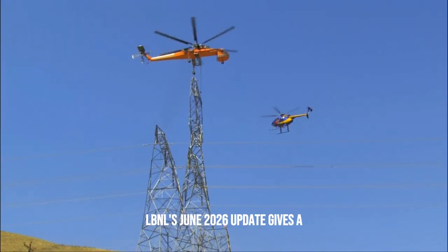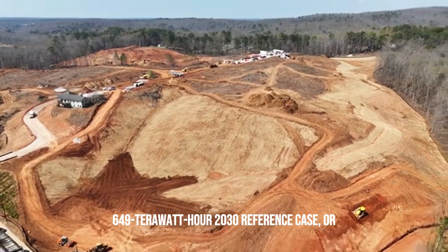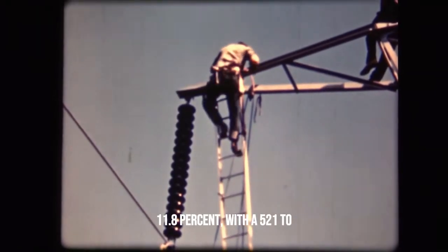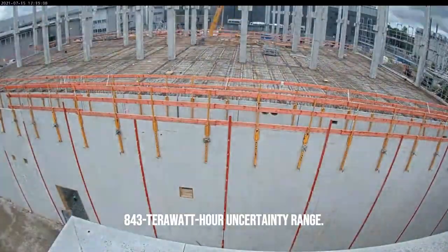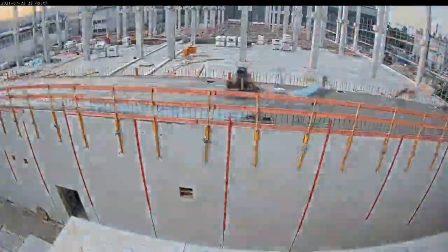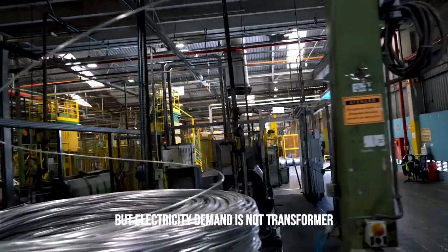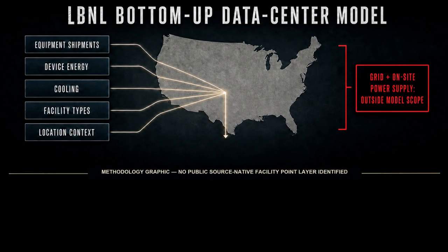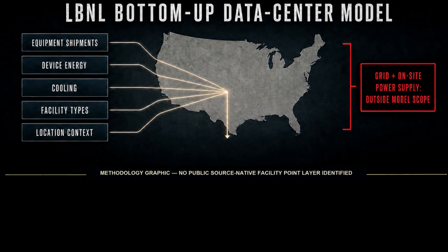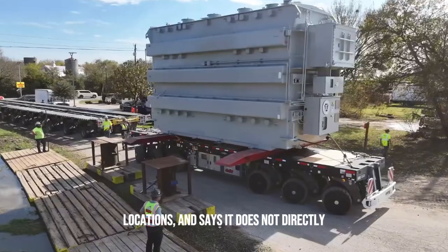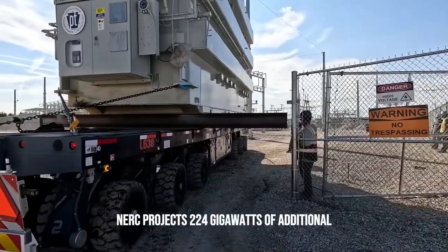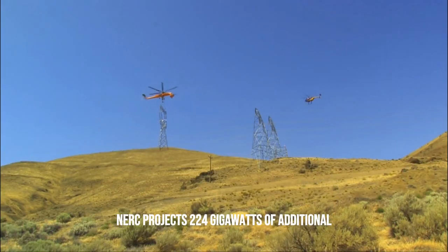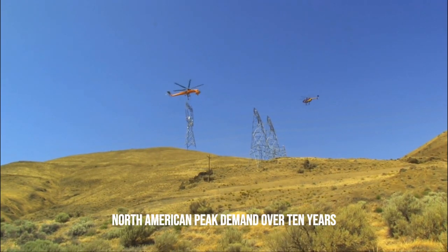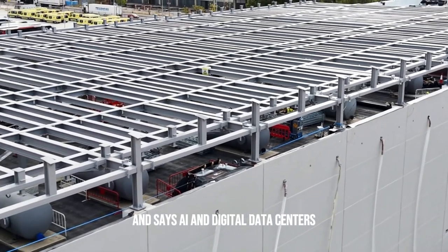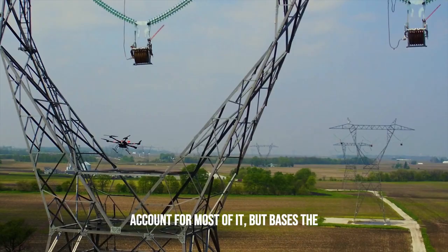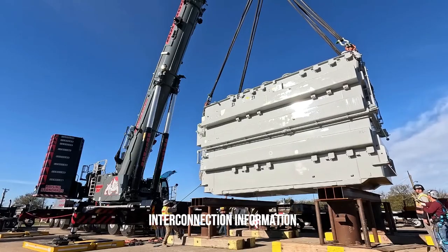LBNL's June 2026 update gives a 649 terawatt-hour 2030 reference case, or 11.8%, with a 521 to 843 terawatt-hour uncertainty range. But electricity demand is not transformer output. LBNL models equipment shipments, device energy, cooling, facility types, and locations, and says it does not directly address grid or on-site supply. NERC projects 224 gigawatts of additional North American peak demand over 10 years and says AI and digital data centers account for most of it, but bases the forecast on utility commitments and interconnection information.